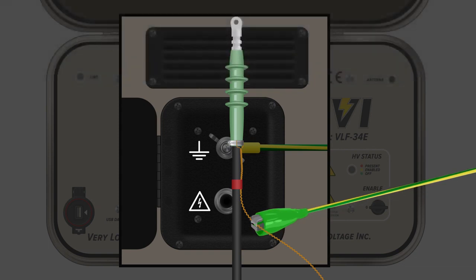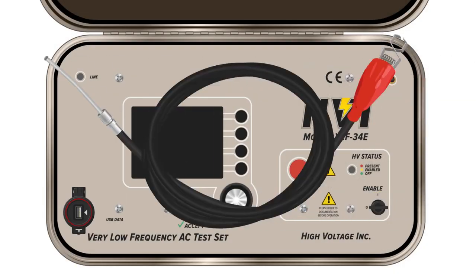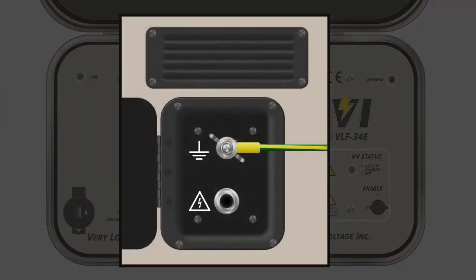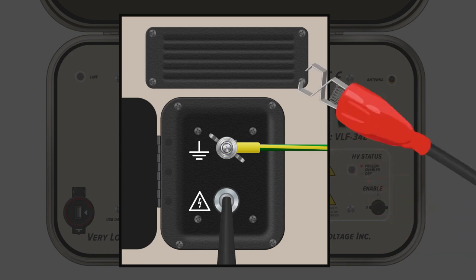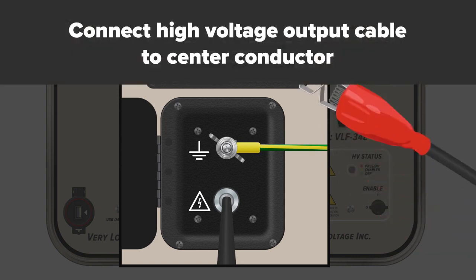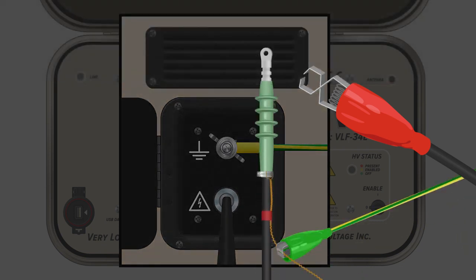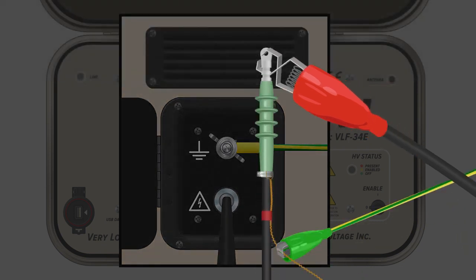After the ground lead has been connected from the high pot to the cable, it's time to connect the high voltage output cable. Insert the high voltage output cable into the high voltage dry well and secure the threaded collar. Take the other end of the high voltage output cable and connect it with the alligator clamp to the center conductor of the cable under test.